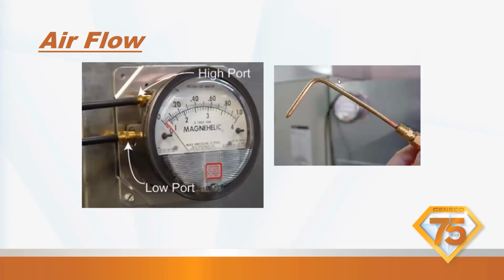This is what a magnehelic looks like. Yes, it's old school. It's the most accurate one out there. If you have an electronic one and you want to verify that you're accurate, you're going to use one of these to calculate the accuracy of your electronic pressure tester, okay? The picture on the right, that's a static pressure probe.